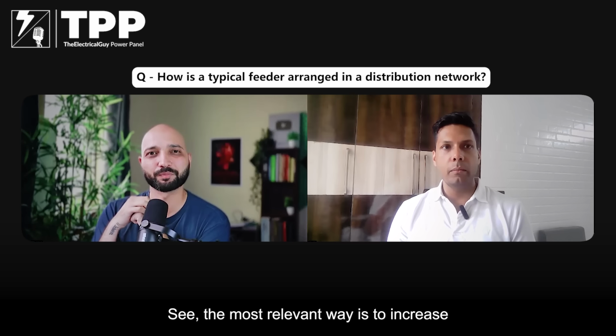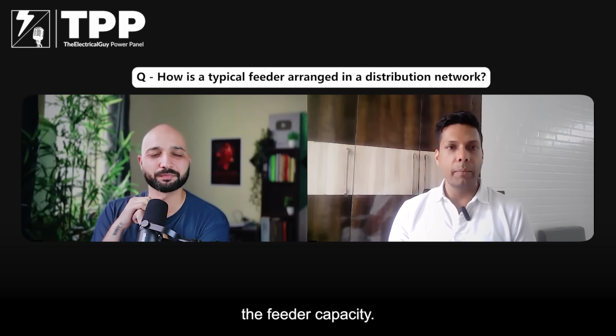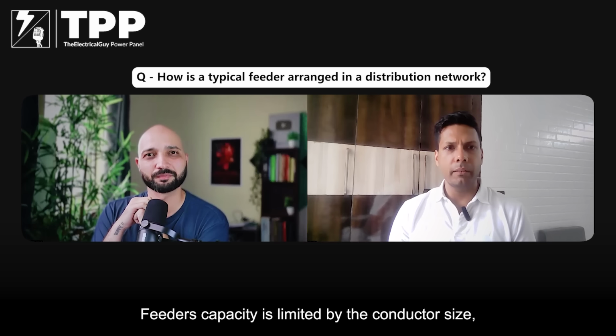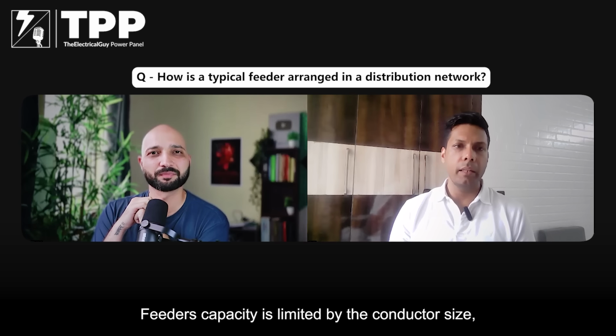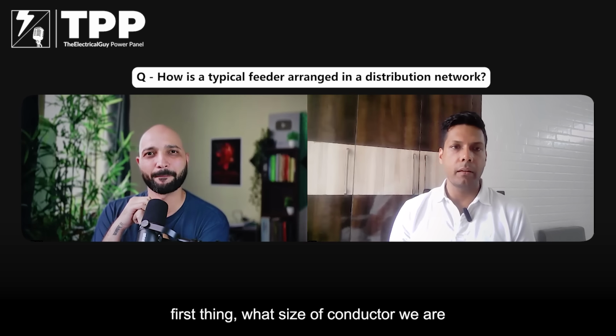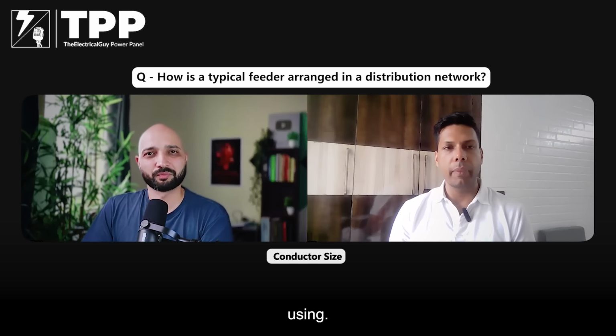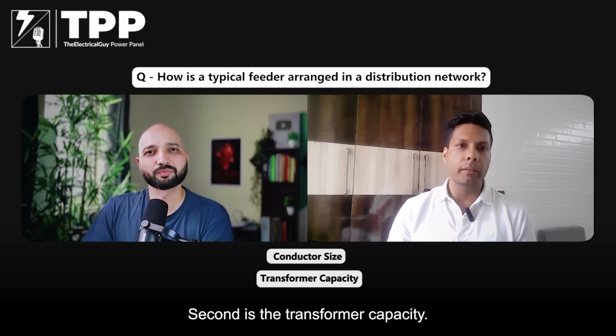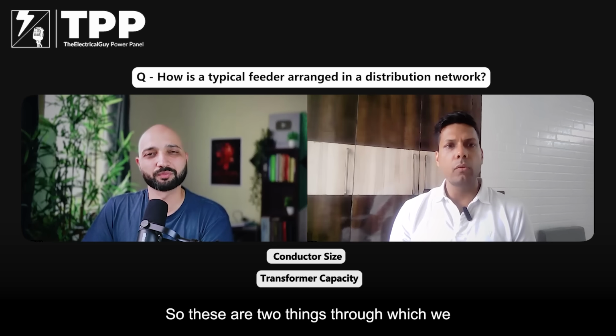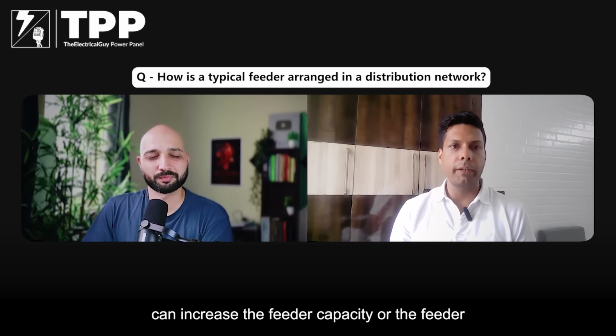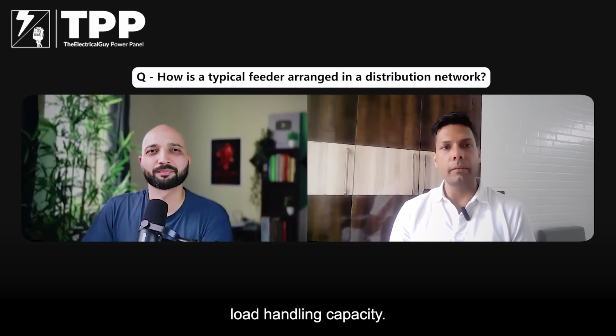See, the most relevant way is to increase the feeder capacity. A feeder's capacity is limited, first, by the conductor size, the size of conductor we are using. Second is the transformer capacity. So these are two things through which we can increase the feeder capacity or the feeder load handling capacity.